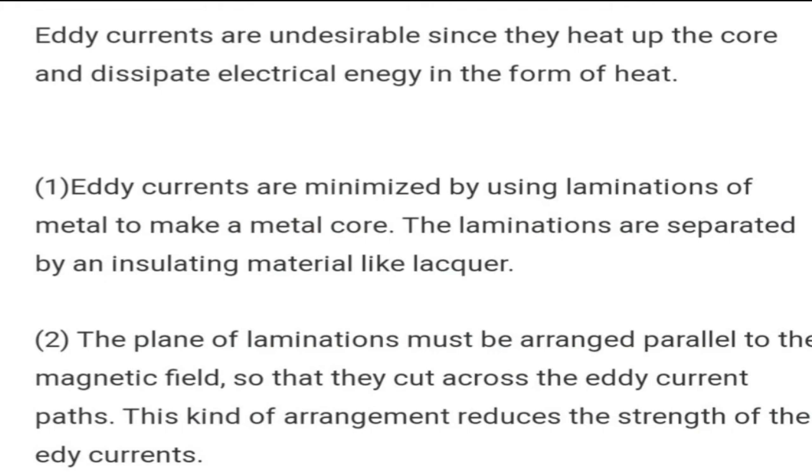And these laminations are coated with an insulating material called lacquer. The plane of laminations must be arranged parallel to the magnetic field so that they cut across the eddy current path. This kind of arrangement reduces the strength of eddy current. So the arrangement of laminations is very important. The plane of laminations must be arranged parallel to the magnetic field.